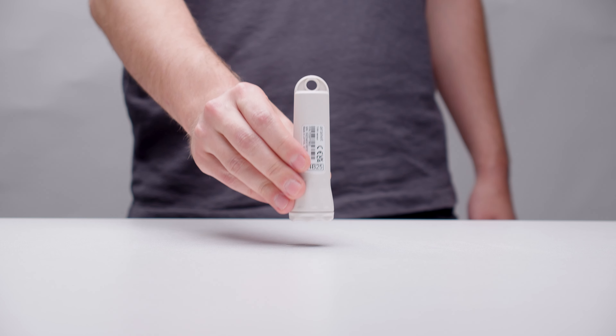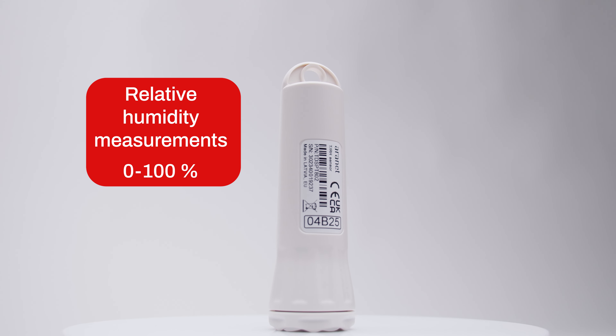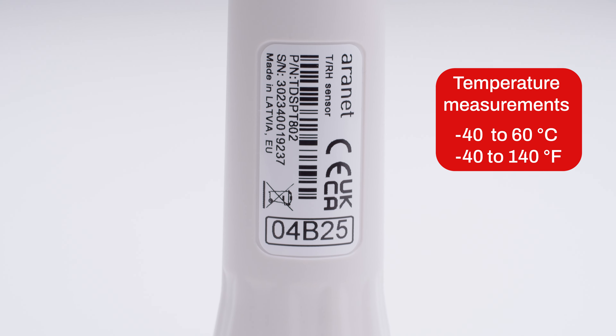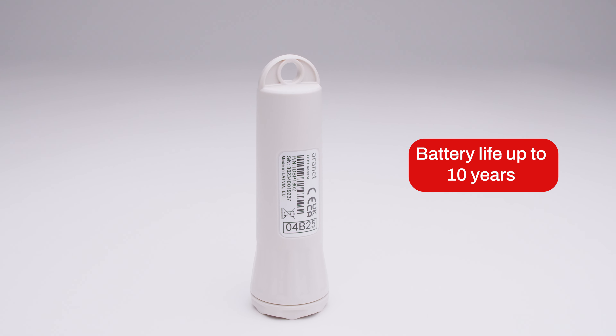This is the Aranet TRH IP67 sensor. It is designed for accurate temperature and humidity measurements in harsh environments. It tracks temperatures in the range of negative 40 to 60 degrees Celsius. The sensor operates wirelessly and is powered by a single AA battery that lasts up to 10 years.